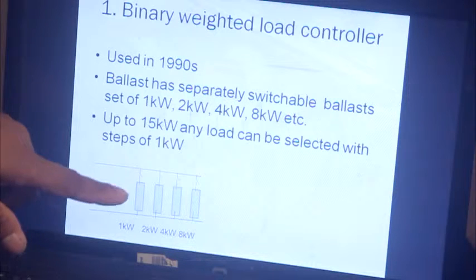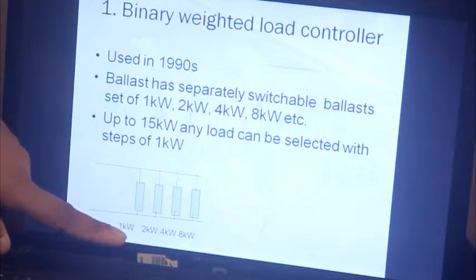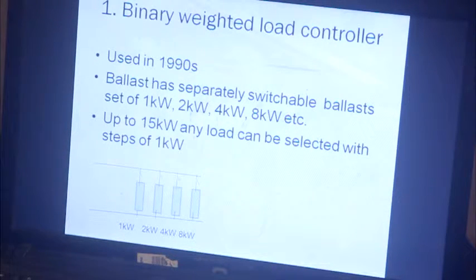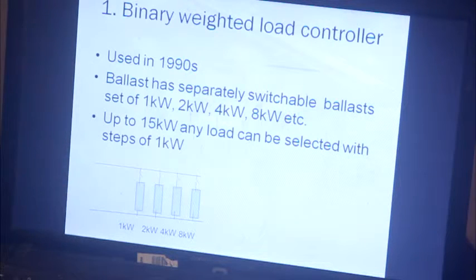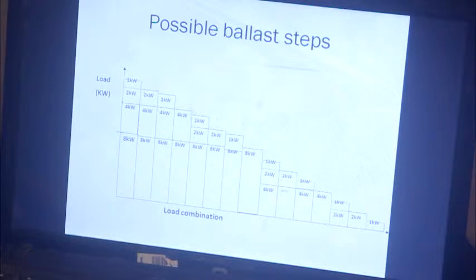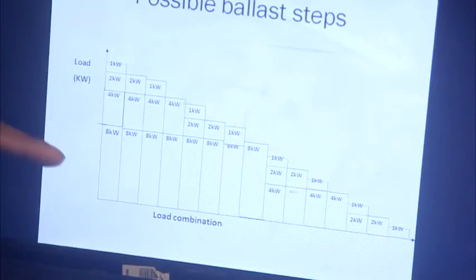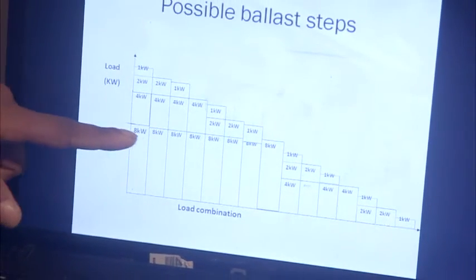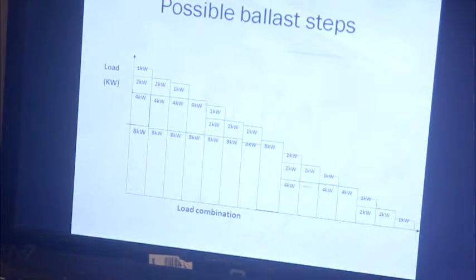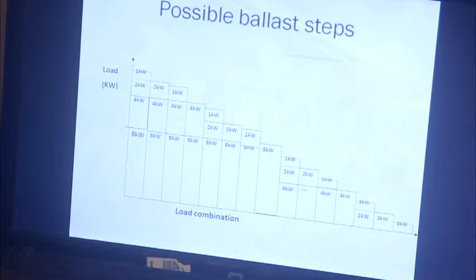From this combination, we can select 0 to 15 kW at any value with 1 kW accuracy. For example, to select 13 kW, we combine 8 kW plus 4 kW plus 1 kW. To select 7 kW, we use 4 plus 2 plus 1. The controller automatically switches these loads on as required to match the excess power. The graphical resolution shows different ballast kW capacities and their relevant combinations. If we want 7 kW, we select 4 kW plus 2 kW plus 1 kW. This is the advantage of the binary load controller.